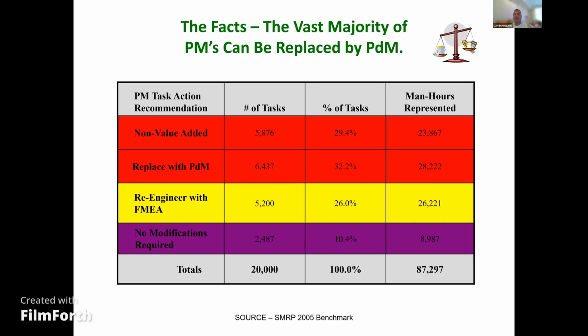If you think about it, in this particular study from 2005 with the SMRP, what we found is that of the total number of tasks, a wide variety of them, 20,000 total, 5,876 of them were non-value added. They were not an actual measurable inspection. So you had a PM written in your CMMS system that said, go out and check this motor, go look at this. But it did not say, go look at this and tell me what the temperature is. There's no quantifiable measurement.